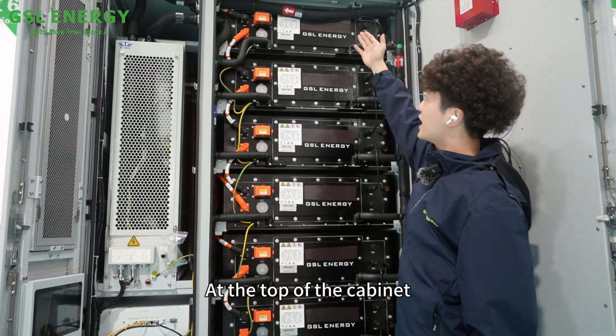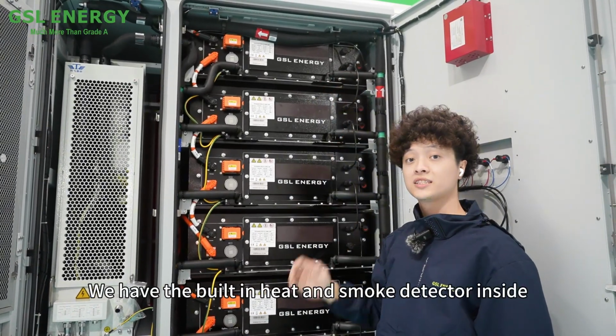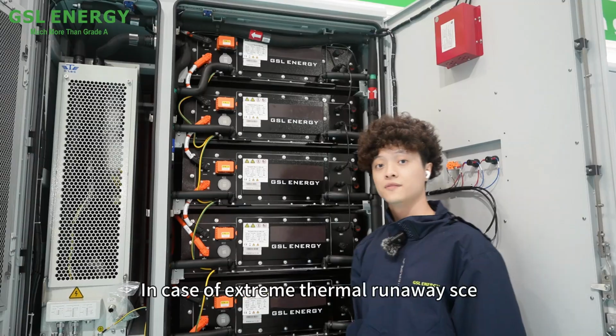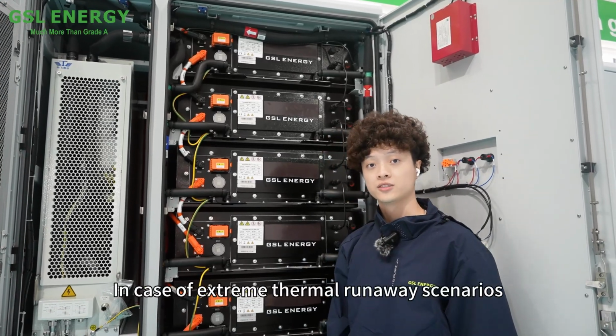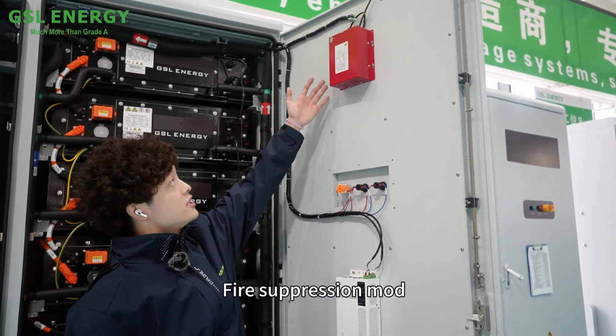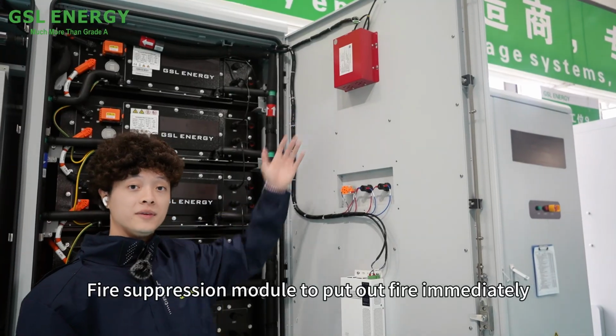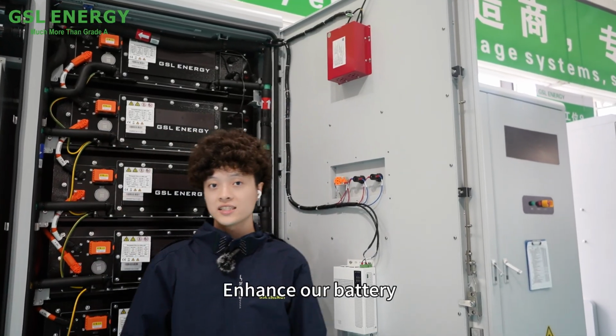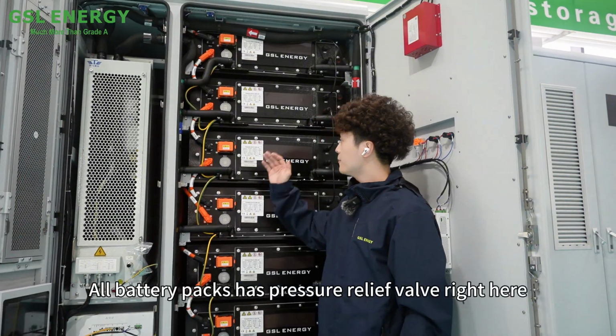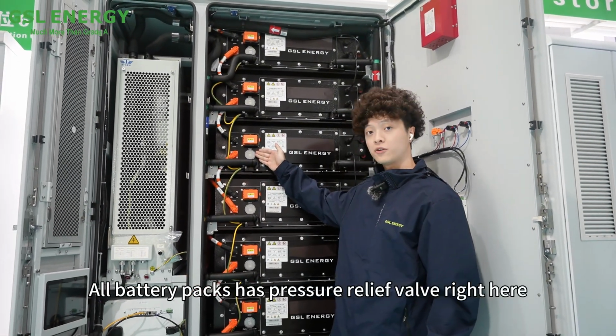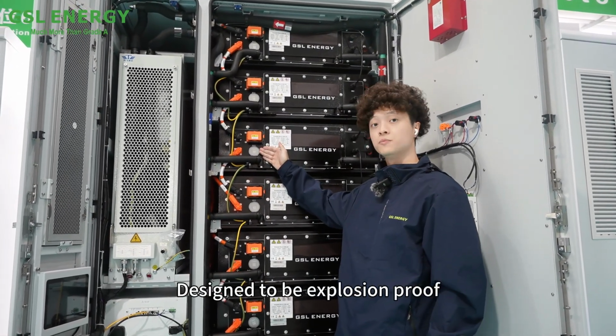At the top of the cabinet, we have the built-in heat and smoke detector inside, in case of extreme thermal runaway scenarios, to trigger the aerosol fire suppression module to put out fire immediately. To enhance our battery safety, all battery packs have a pressure relief valve right here, designed to be explosion-proof.